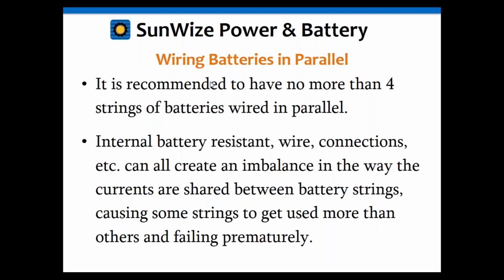It is recommended to have no more than 4 batteries in parallel, though this can vary by manufacturer. Some say 5 or 6, some say as much as you want, but generally you want to try to keep it around 4 or less. Actually, I'd say just 1 or 2 for the most part. You can go up to 4 if you need to, but try to keep that minimized. If you need a bigger capacity, go to a bigger battery.